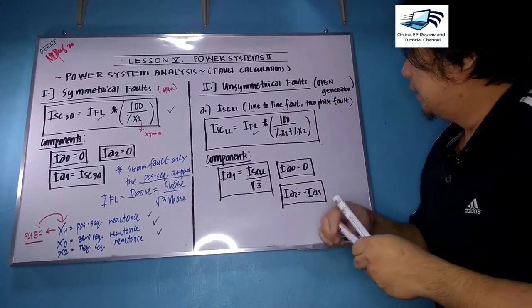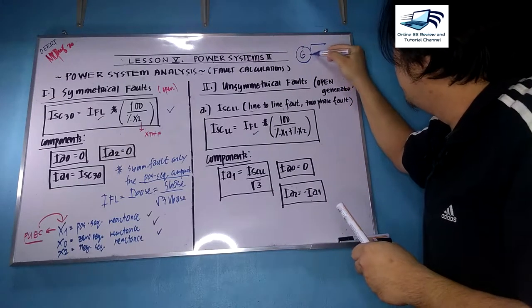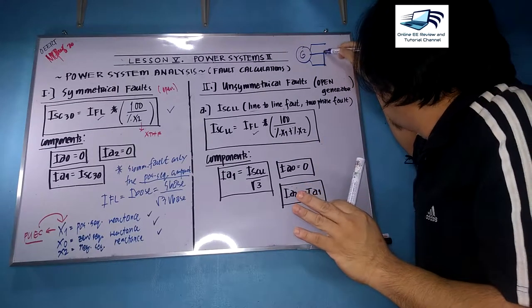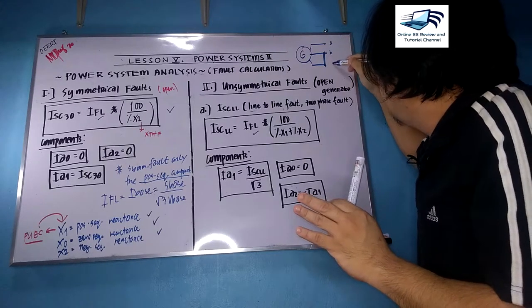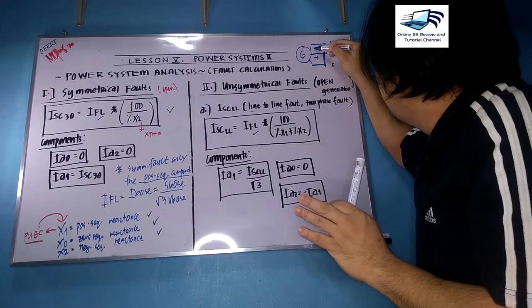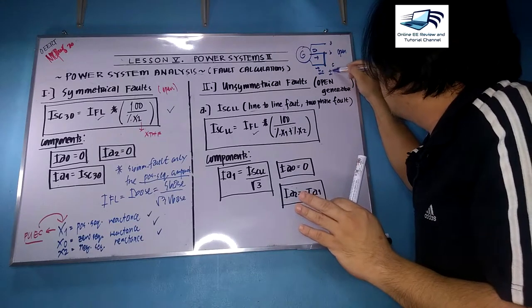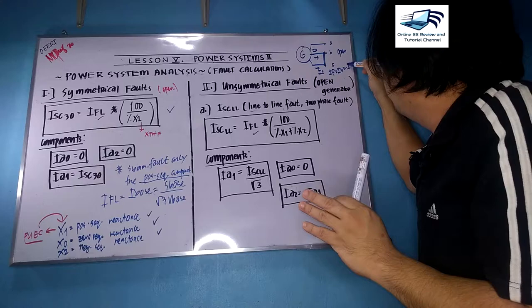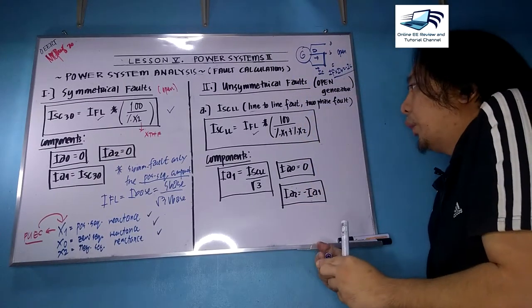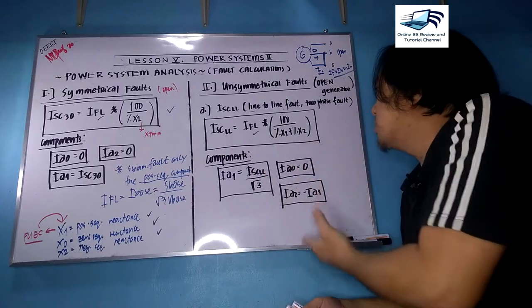For a line-to-line fault, if you have a generator with phases A, B, and C, with A open, you short-circuit B and C. The fault current is derived here which is equal to IB, which is the negative of IC. So ISC line-to-line is a line-to-line fault, sometimes called a two-phase fault.